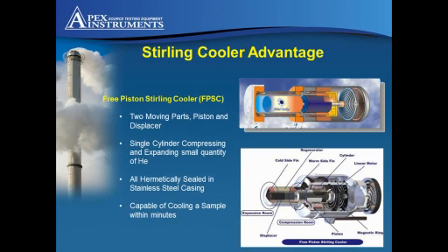Moisture has to be removed from the sample. We use the high-performance Stirling cooler, a closed system. The Stirling cooler offers high-efficiency moisture removal. Chosen for its ability to operate in extreme ambient conditions, for example, within an annulus where summer temperatures can be extremely high, and winter temperatures can be a little on the chilly side.